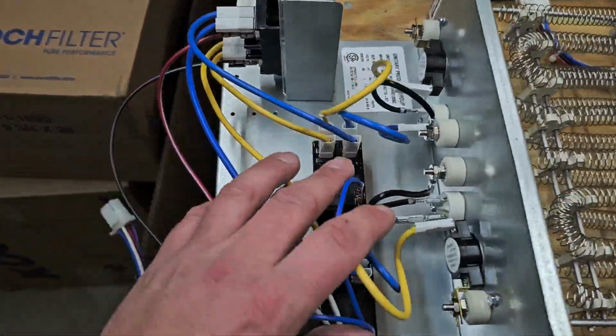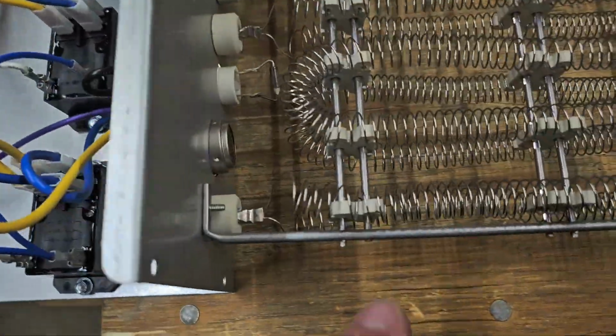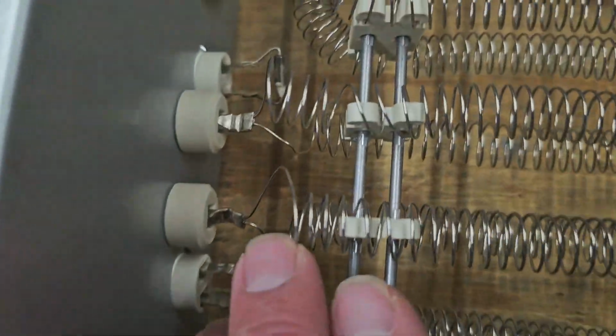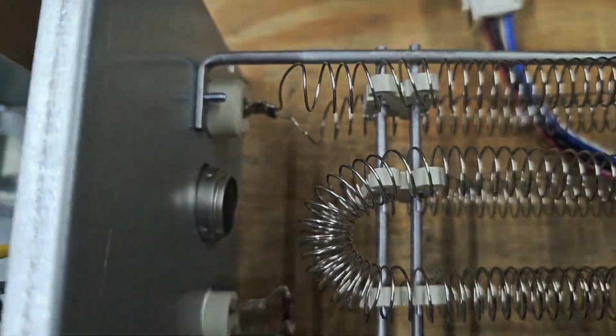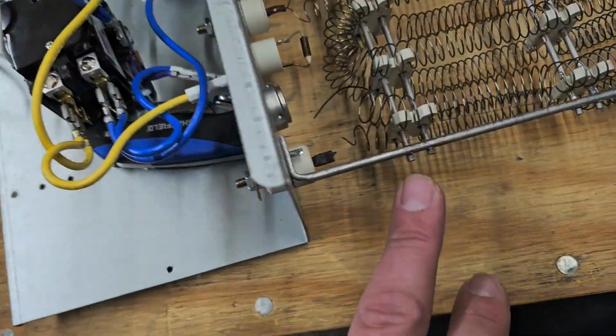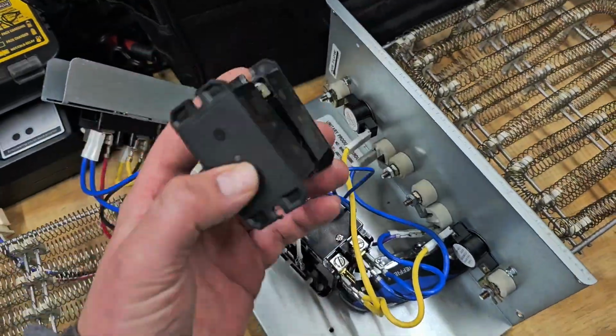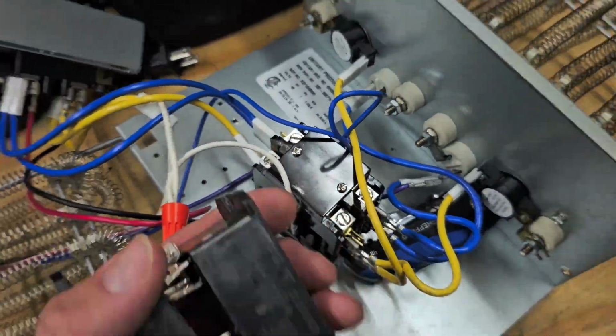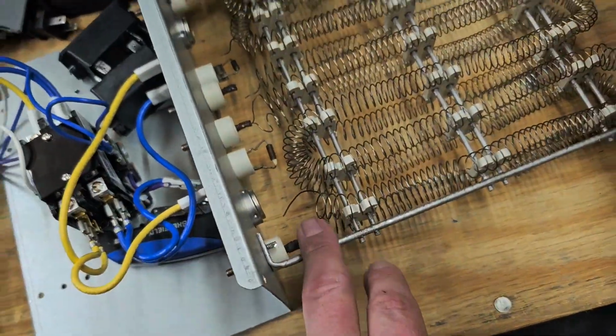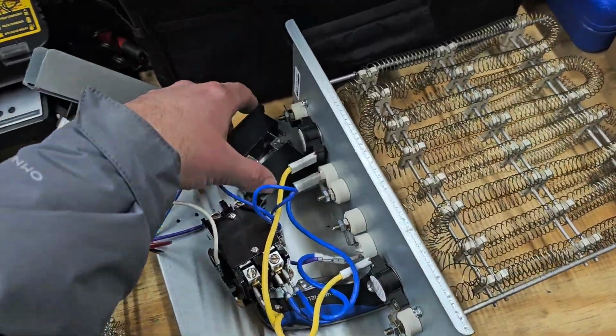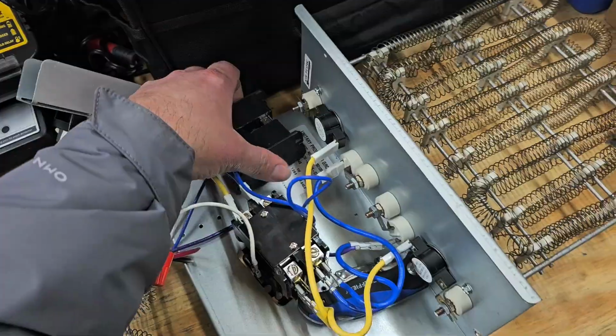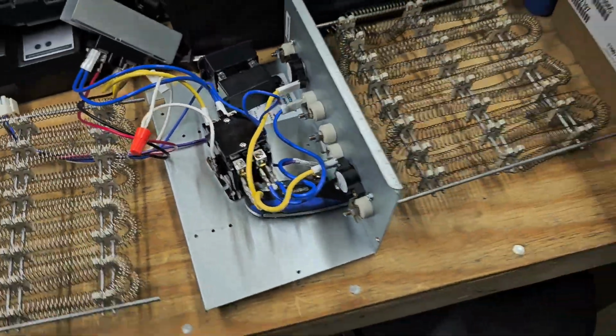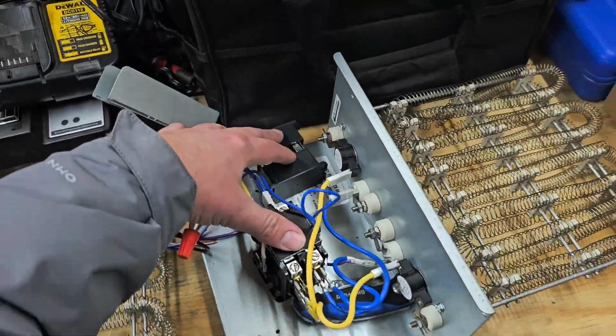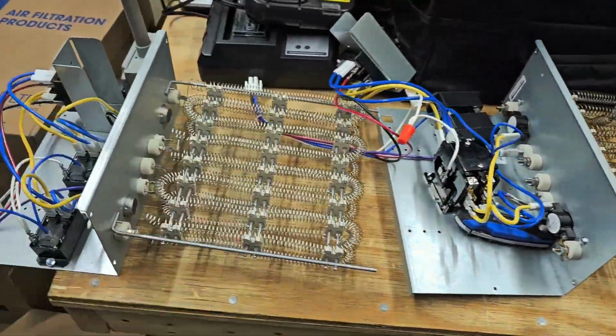I'm very happy. I've got a brand new heater kit. See, no broken wires. No broken wires, and you can see it's brand new, no rust. Not like the old one with those broken wires, with that rust, broken wires. And I ended up replacing the relays with a contactor because I didn't see the broken wires, and I thought, how is this not working? The relays were closing, so I thought, you know what? I'm gonna replace it with a contactor. If you wanna learn more about relays, contactors, transformers, I'll put a video down below for you.